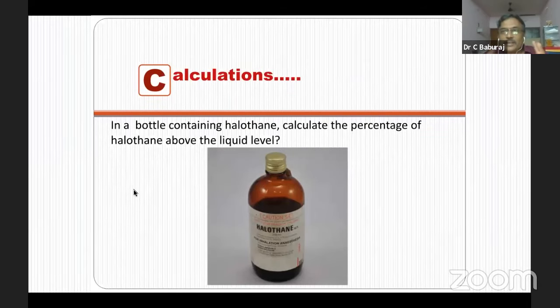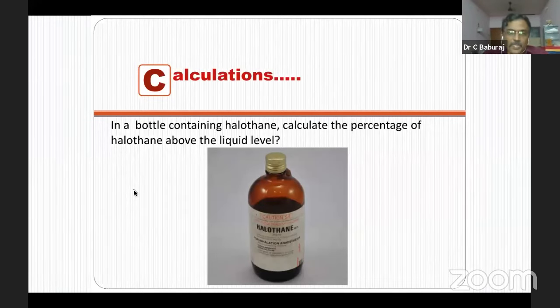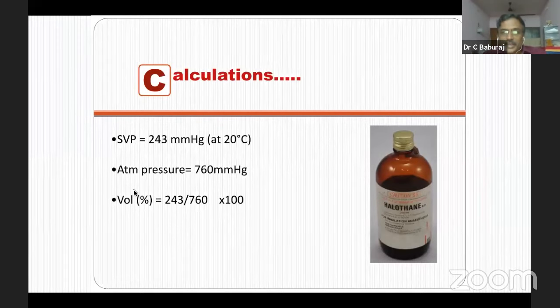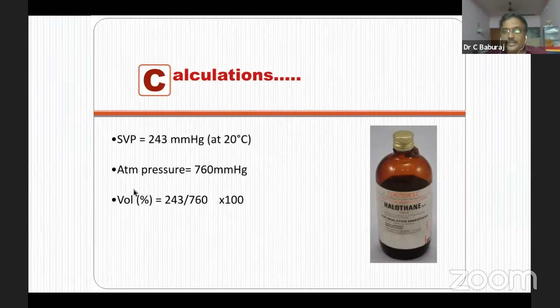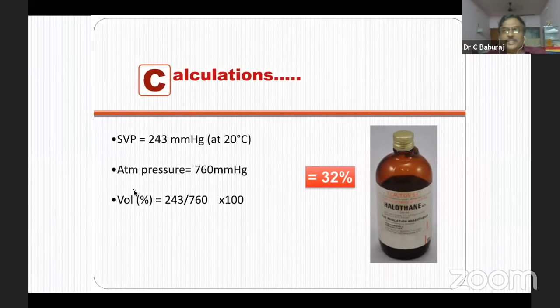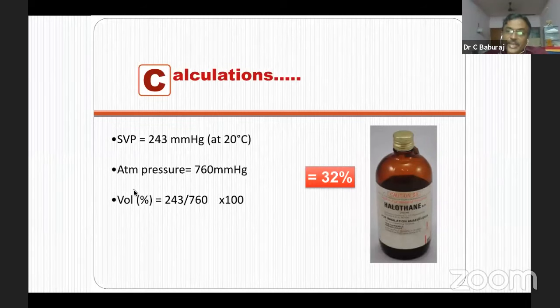A practical example: you have a bottle of halothane. What is the percentage of halothane vapor above the liquid level? SVP of halothane is 243 mmHg at 20 degrees centigrade, atmospheric pressure is 760 mmHg. Using the formula 243/760 × 100, that gives approximately 32%. So when you open a bottle of halothane, about 32% of halothane is present in the vapor above. The importance of this will be explained when describing variable bypass vaporizers.